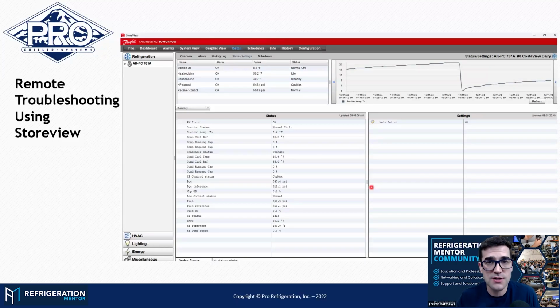If you plan on changing something, you've got to have someone there, because for some reason, all of a sudden that high pressure valve closes. You change something and the compressor is still running, and you may pop the relief, and now you get no CO2 in the system. You know what I mean? That could be an issue.